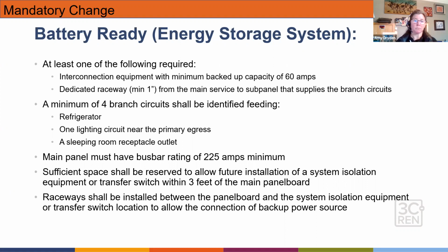To be able to accommodate this energy storage load, there are some additional requirements in terms of location, and ensuring that you have space for the transfer switch, which means cutting yourself from the grid, so now you're only operating on battery, right? You need that transfer switch for that isolation. And you want the raceway installed between the panel board or your main panel and where that potential equipment can be located, to allow an easy run of conductors in the future to support that battery install. Next slide.